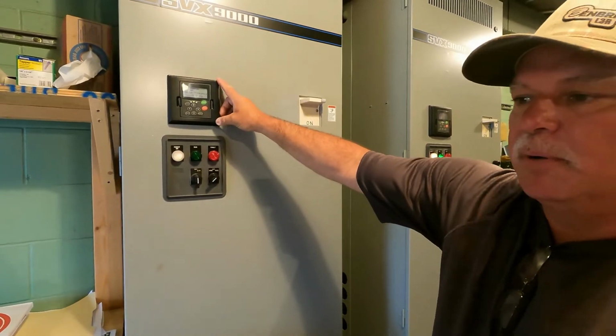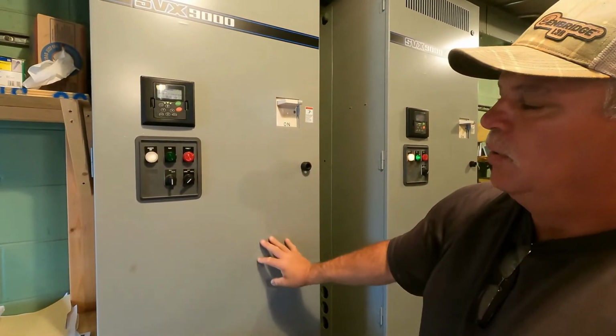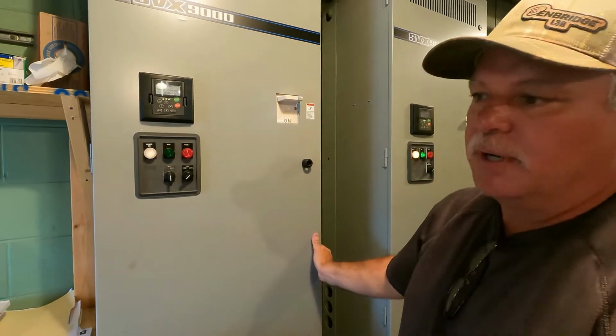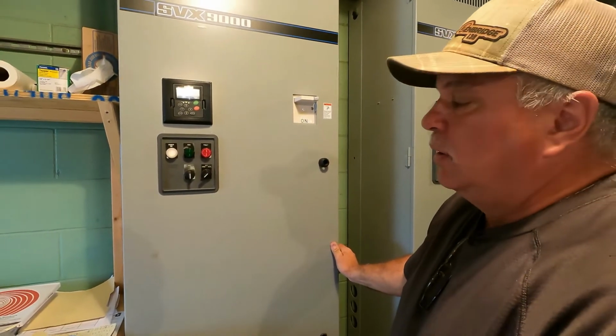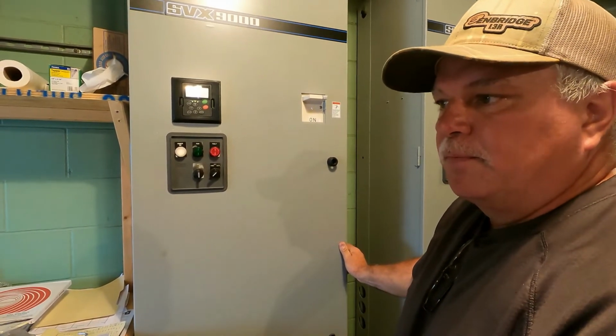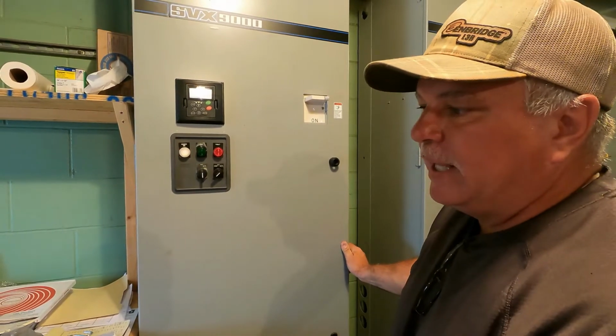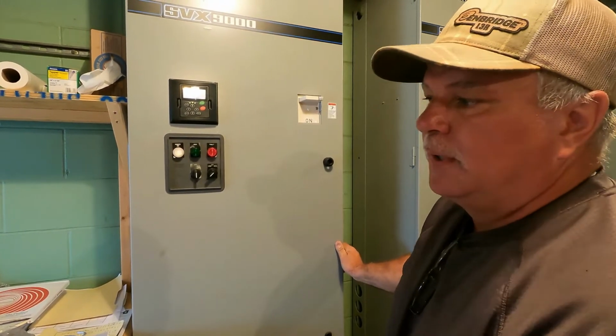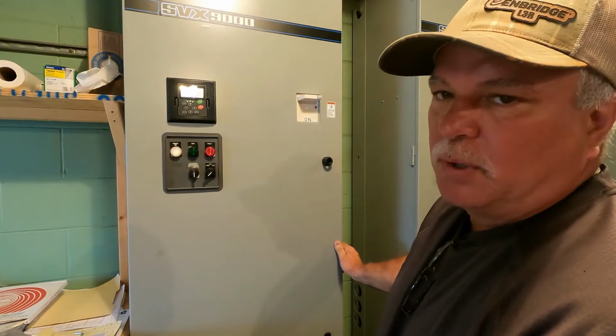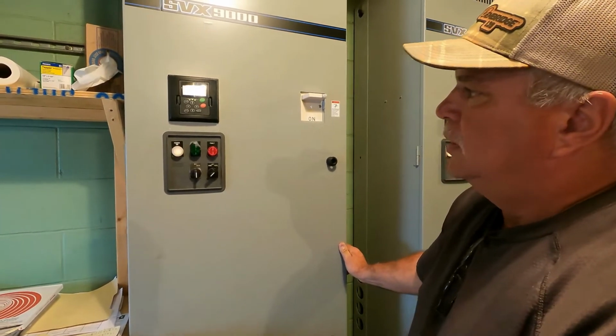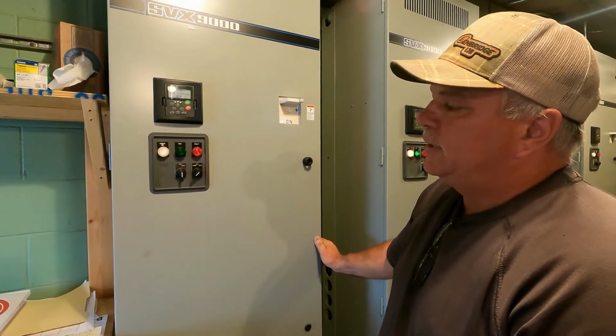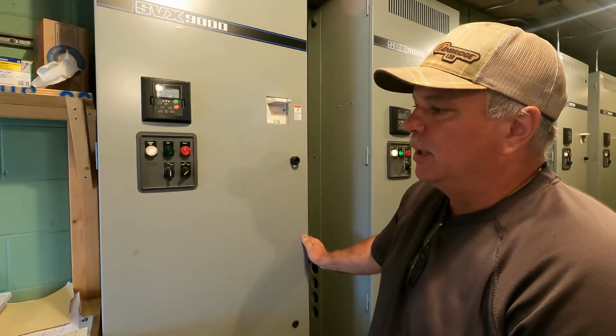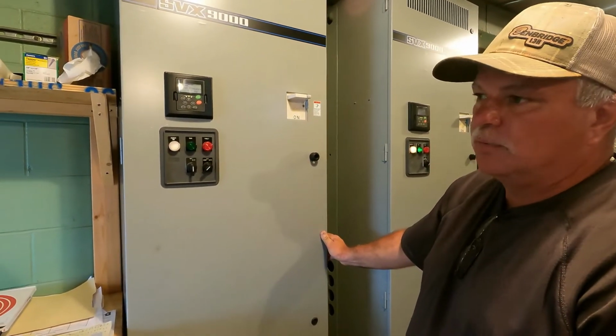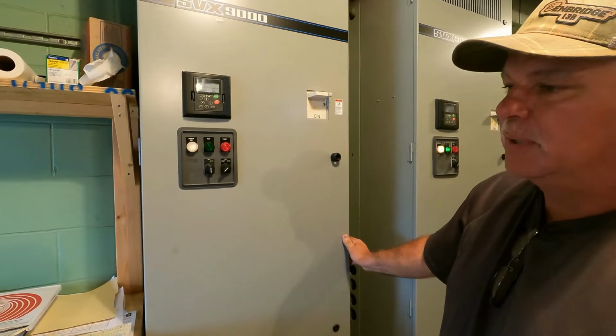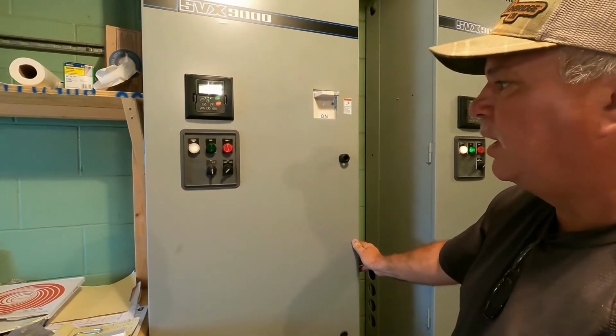You can set your minimum, your maximums, and what this panel actually does, there's an inverter inside here that adjusts the speed of the pump for the flow, and that eliminates the constant on-off of the pump due to a float, and it really tends to be more energy efficient in the long run as far as being able to avoid the demand charges, the constant on and offs of a float operated pump.